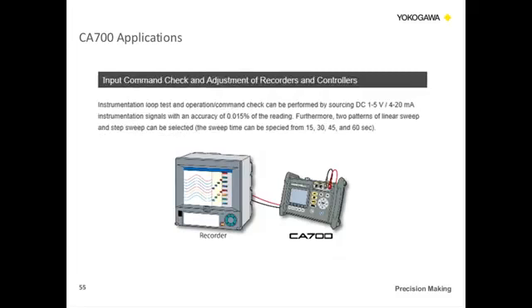And keep in mind, although this is the most accurate pressure calibrator out there, because of the source and measure function, it's almost like buying 2 calibrators in one. You've got a voltage and current calibrator and also a pressure calibrator. A lot of times you just need to source a 4 to 20 milliamp signal, and for calibrating a recorder input, the CA700 is perfect.